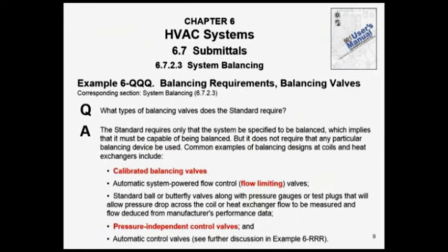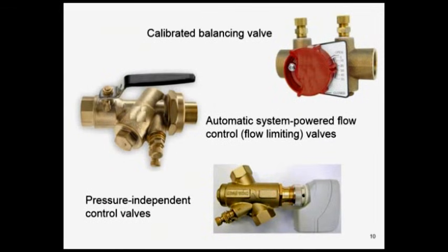Another item is pressure independent control valves, PIC valves. Yes, pressure independent control valves are mentioned in the ASHRAE 90.1 User's Manual as a possible way of balancing because they have a constant pressure drop across them. If you know the position of the valve, you know the flow rate in GPM. Therefore, you may see more people using PIC valves as a way of balancing in particular situations. So let's keep looking a little further. Here are some typical pictures of what these devices look like. A lot of various vendors make these types of devices, and they are on the market, readily available. A lot of them have Cv lookup packages to give you something you can specify and make sure you have the instrumentation you need to balance your system.